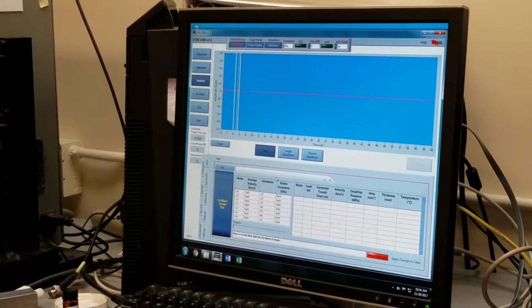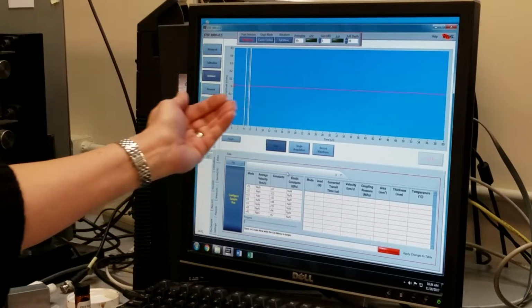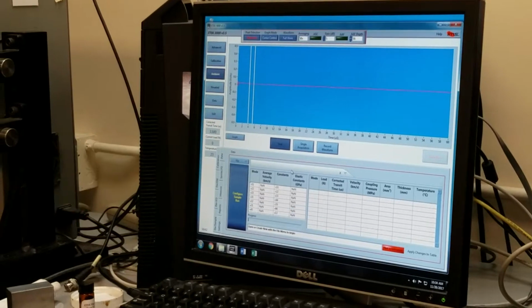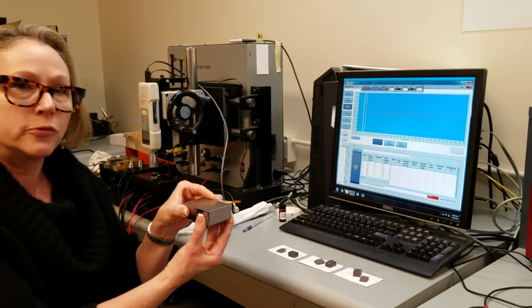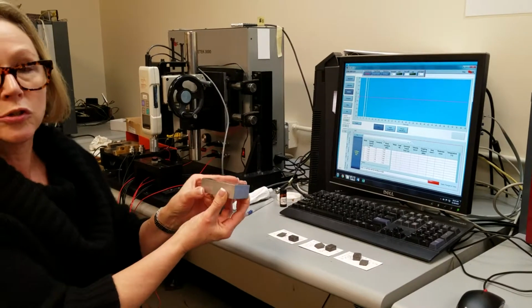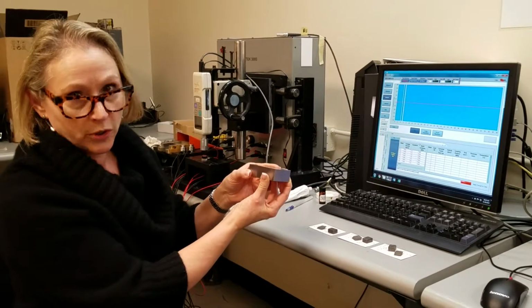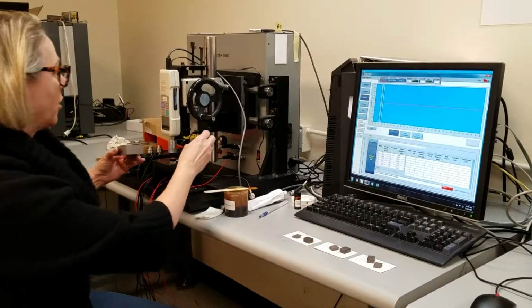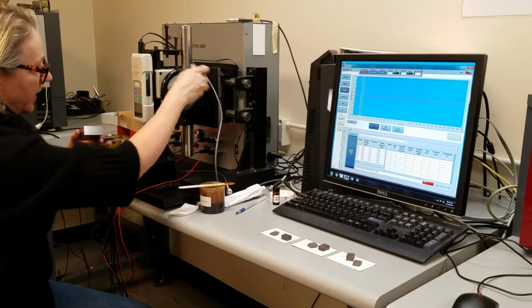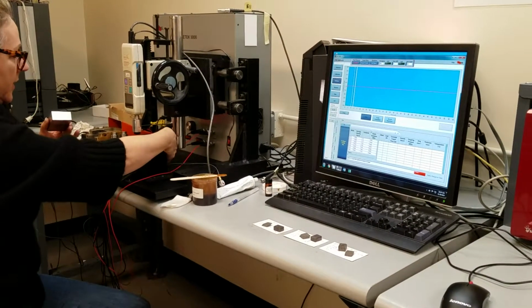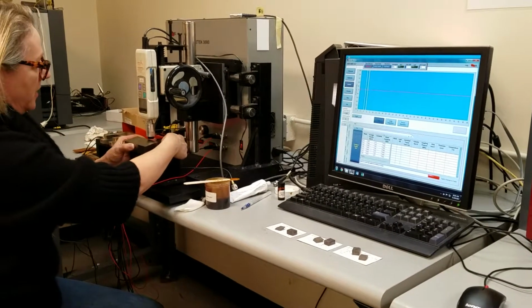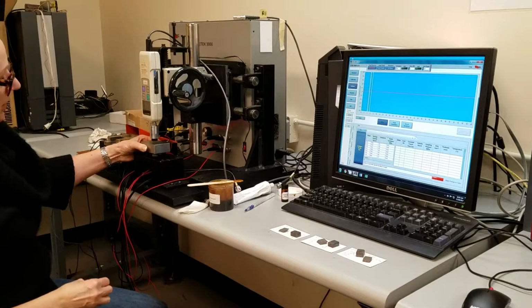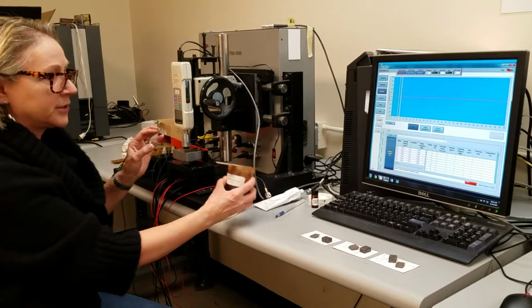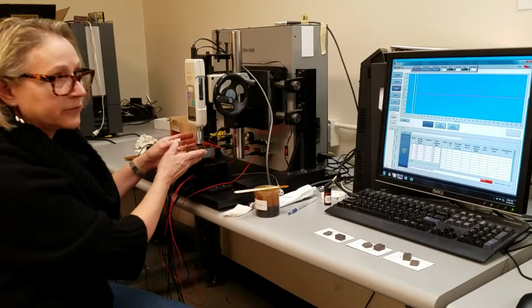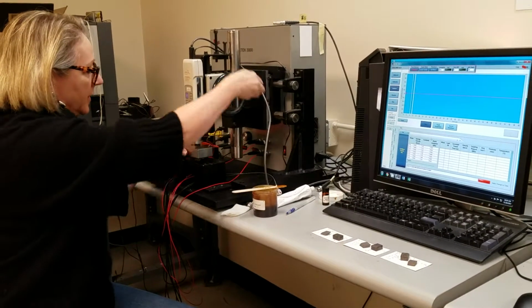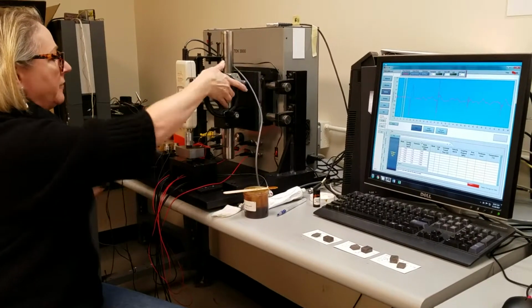As I mentioned, the first thing that we're going to do is a calibration, and we will be looking at the ultrasonic waveform in the blue area of the screen. So I take my 1, 2, 3 gauge block, and we're going to be measuring essentially the ultrasonic transit time through the 1-inch direction of this. I go over to my stage, and I have my shear wave transducers in place, and I'm going to put my gauge block in between the transducers. I do have a little bit of SWC couplant either on the surface of the gauge block or on the transducers themselves, and I am going to apply 700 newtons of load.